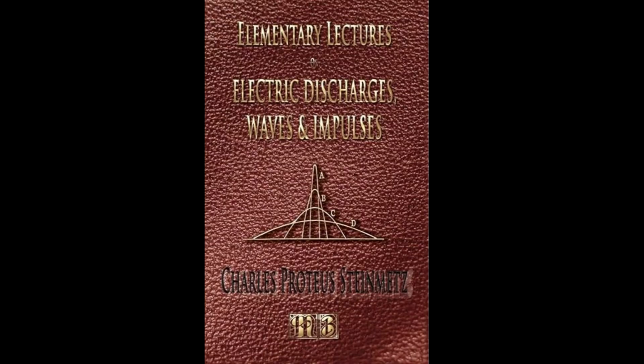21. The conditions with a single-phase short circuit are different, since the single-phase armature reaction is pulsating, varying between 0 and double its average value, with double the machine frequency. The slow field transient and its effects are the same as shown in Figure 21, A to D. However, the pulsating armature reaction produces a corresponding pulsation in the field circuit. This pulsation is of double frequency, and is not transient, but equally exists in the final short circuit current.